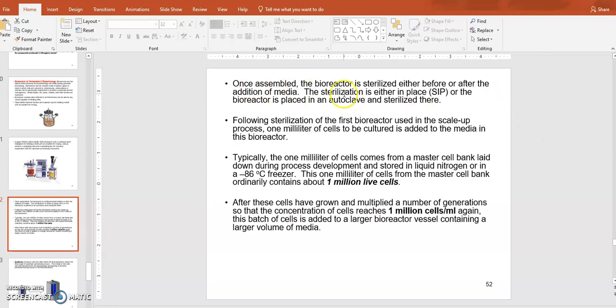Assembly of the bioreactor is important because you have to do it aseptically. After the bioreactor is assembled aseptically, then you're going to introduce your cell line. It depends on the size of the bioreactor. You can sterilize it within an autoclave, or if it's too big, you're going to have to do it using CIP, clean in place, by shooting pressurized water and cleaning solution, and rinsing it. Then at the end you have to sterilize it by doing a sterilization in place, steam in place. You'll generate pressurized steam in there and close it, and that's how you can sterilize it. So you have to make sure that you do it well.